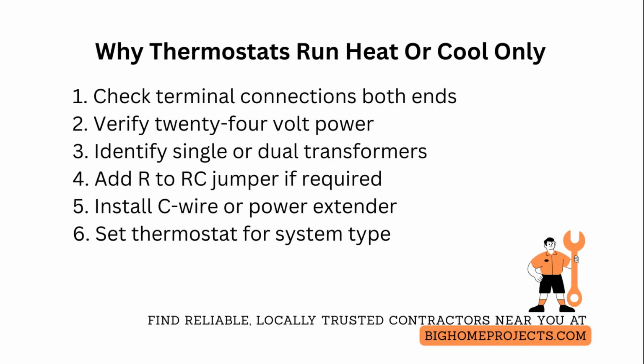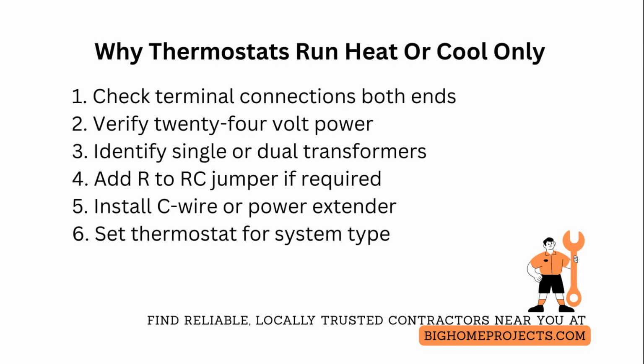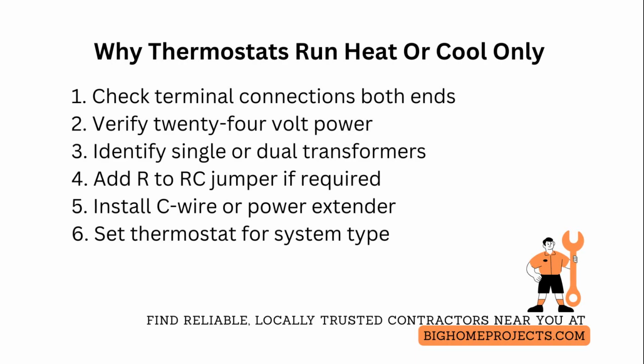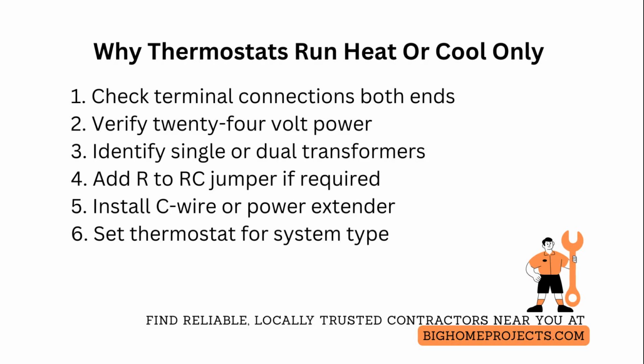If set to conventional heating and cooling, the thermostat may not energize the reversing valve and will only operate one mode. Check the indoor unit and outdoor condensing unit contactor coil. If the thermostat energizes Y, but the contactor does not pull in, test for blown fuses or open safety switches like low pressure or float switches in the drain pan that can interrupt cooling.